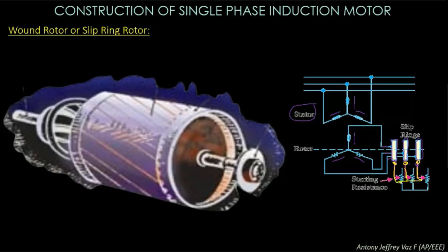Now the slip rings are connected with the brushes. You can see this is the brush. At the end, you will have brushes, and from the brushes the supply is taken out. It is connected to a rheostat, or these three phases are short circuited. This is the construction of the slip ring induction rotor.